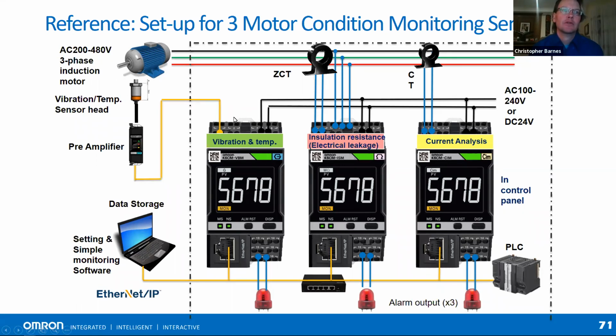If it picks up a difference in ambient temperature, it compares this temperature with the motor temperature and looks at the difference between ambient and motor temperature. Sometimes the motor temperature is rising, but the room temperature is also rising because it's a hot day. What really matters is that as the motor starts to fail, you'll see it in the vibration and the temperature. It helps having both pieces of information together, especially with different failure modes.